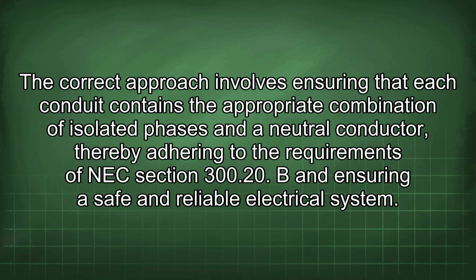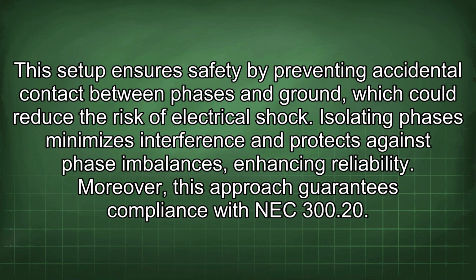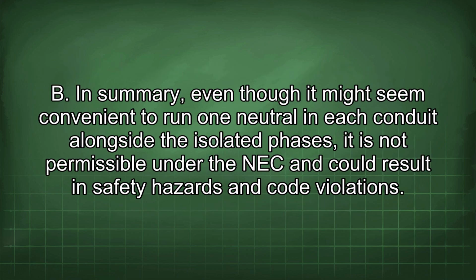The correct approach involves ensuring that each conduit contains the appropriate combination of isolated phases and a neutral conductor, thereby adhering to the requirements of NEC Section 300.20, and ensuring a safe and reliable electrical system. This setup ensures safety by preventing accidental contact between phases and ground, which could reduce the risk of electrical shock. Isolating phases minimizes interference and protects against phase imbalances, enhancing reliability. Moreover, this approach guarantees compliance with NEC 300.20. In summary, even though it might seem convenient to run one neutral in each conduit alongside the isolated phases, it is not permissible under the NEC and could result in safety hazards and code violations.